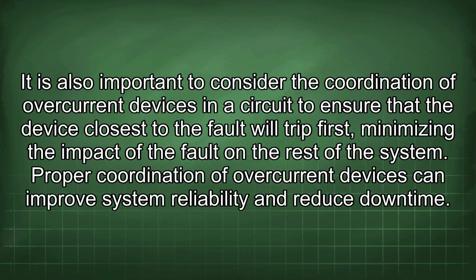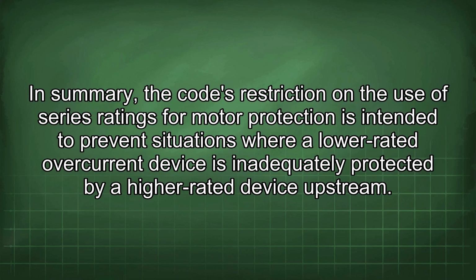It is also important to consider the coordination of overcurrent devices in a circuit to ensure that the device closest to the fault will trip first, minimizing the impact of the fault on the rest of the system. Proper coordination of overcurrent devices can improve system reliability and reduce downtime. In summary, the code's restriction on the use of series ratings for motor protection is intended to prevent situations where a lower-rated overcurrent device is inadequately protected by a higher-rated device upstream.